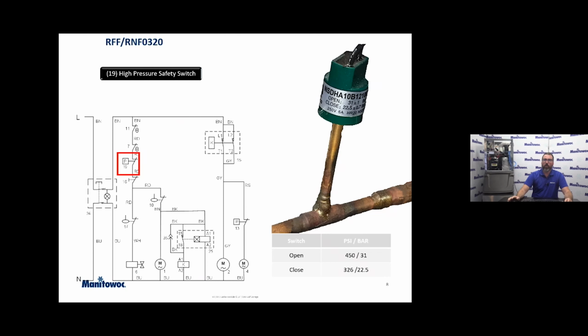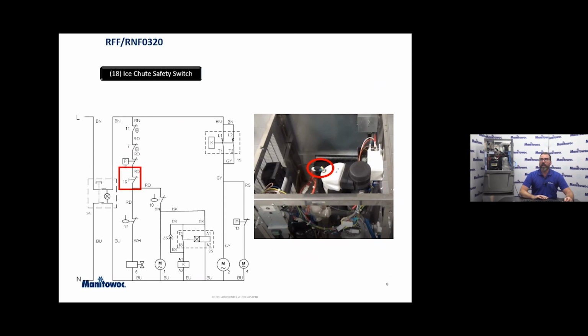But with that being said, we're going to want to make sure that that's closed, of course. We have that ice chute safety switch that I talked a little bit about before. Basically, that is on the discharge of the evaporator. What that's looking for is to make sure that we don't have ice backed up into the ice chute itself. If we do, we probably have a blockage, or we simply have a full bin and we need to shut that machine down, of course. That would be if our bin thermostat switch had failed for some other reason. That's a backup safety for that.